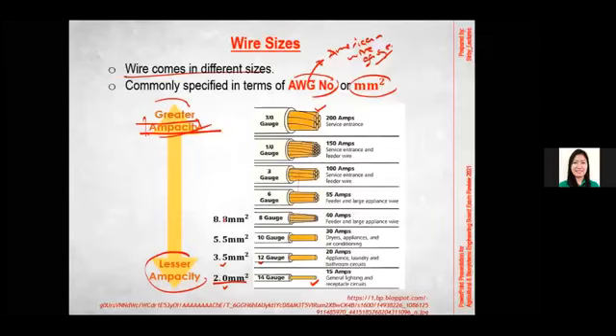There's also information regarding the capacity in numbers, let's say 15 amps, 20 amps, or 30 amps, and the applications. For general lighting and receptacle circuits, this is the typical wire size. If you have appliances with increased loads, you'd use gauge 12, and much higher loads would mean gauge 10. For feeder wires and large appliance wires, that's gauge 8.